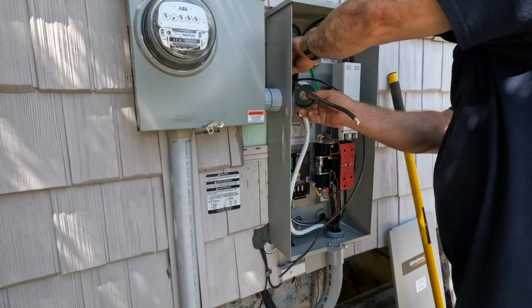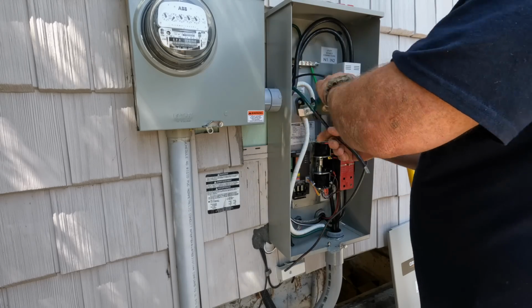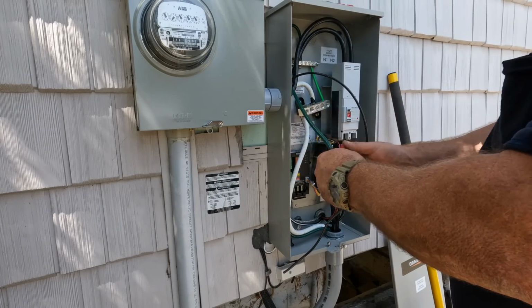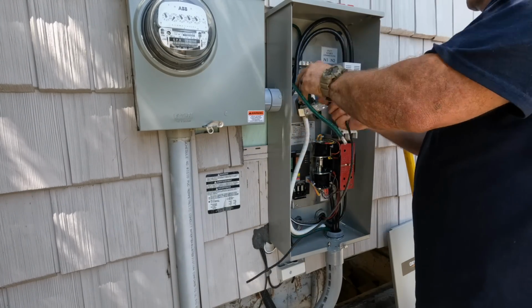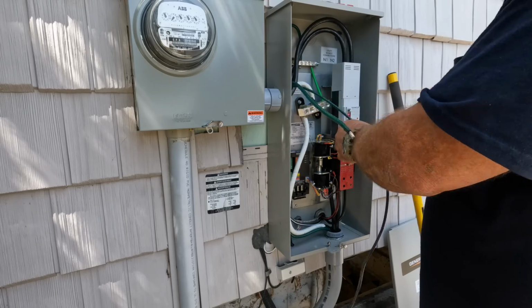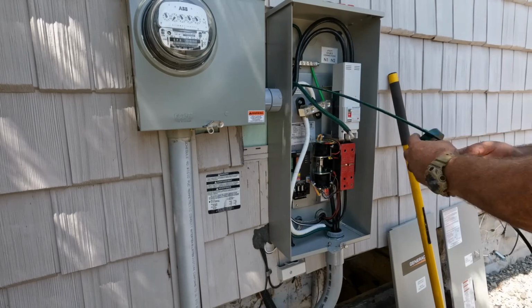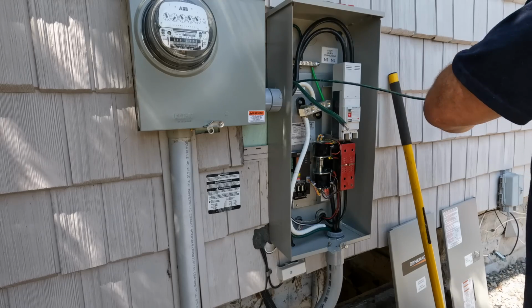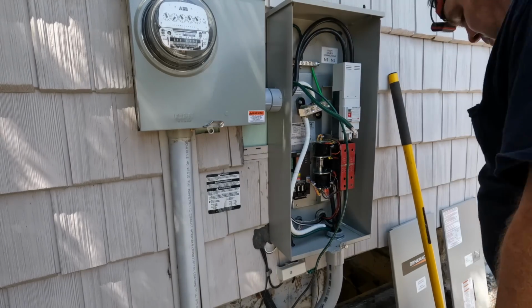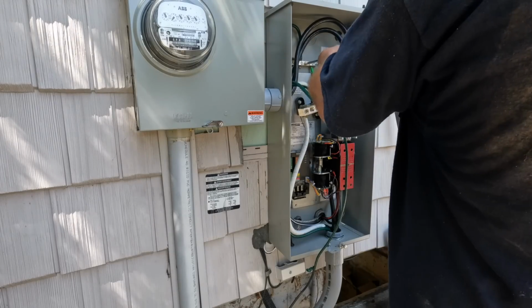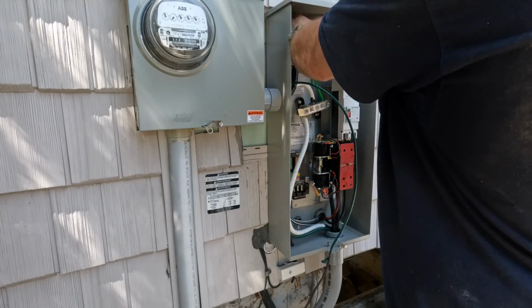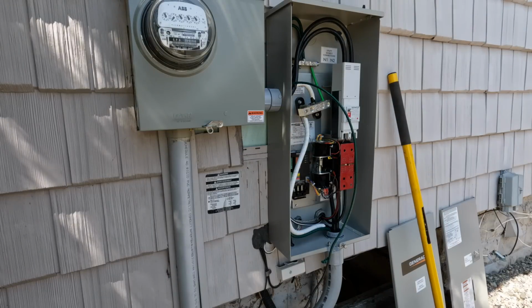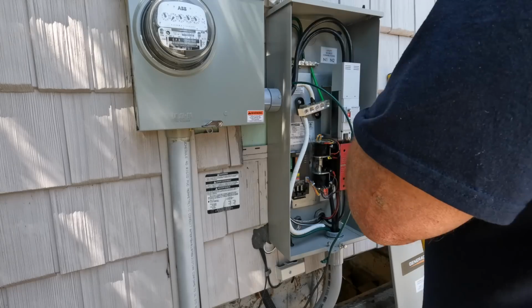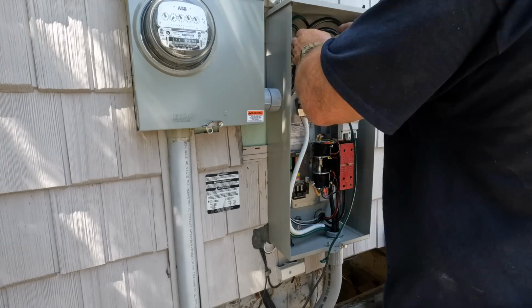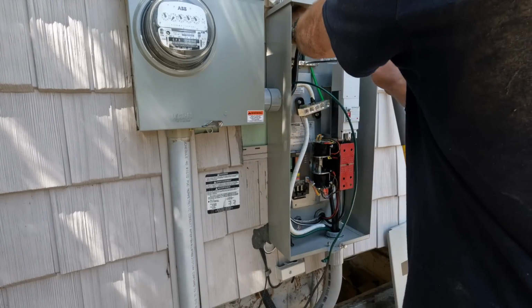Now, there's no meter in the basement, so I'm not sure where the metering gets done. Maybe there's no meter on the outside here. I'm not exactly sure, but there was no meter on the inside. And they have an on-demand water heater that you'll see momentarily when we get down to the basement. But here, I'm just preparing to terminate the grounding electrode conductors on the ground bar inside the automatic transfer switch, which is bonded to our system neutral, which is also inside the main disconnect.